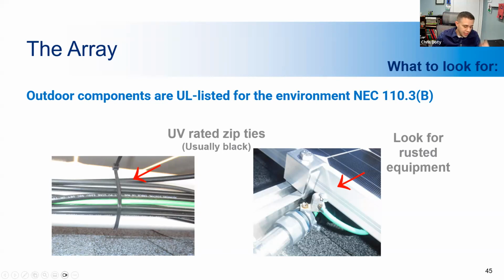And on the right, it may be a little bit difficult to see, but you can see this screw connecting the lug to the conduit is rusting. That means they did not use an outdoor rated screw. That will eventually corrode, rust away, and it will likely come disconnected, and then you won't have a grounded system, which is obviously not a good thing. So that's definitely something to look for if someone's taking a shortcut, using a non-weather rated screw. That will eventually cause a failure.